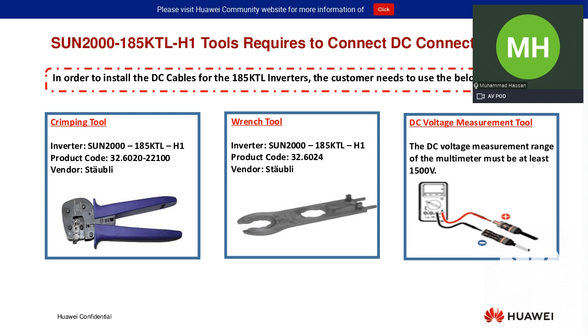The third tool you need is the DC voltage measurement tool. Make sure you use a multimeter rated for at least 1500 volts, and you need to check the polarities of the DC strings before connecting the DC connectors to the DC strings, because customers don't care about the polarities, and when they connect the DC cables to the input of that inverter, it damages the inputs. If the input of that inverter is damaged, we do not replace that kind of inverter, because this is an installation problem. So the customer needs to focus on the polarities as well.